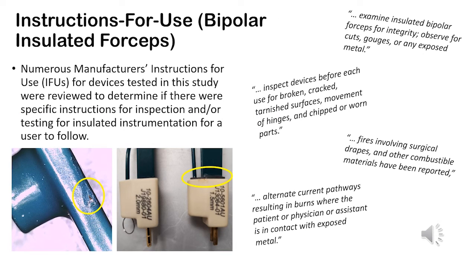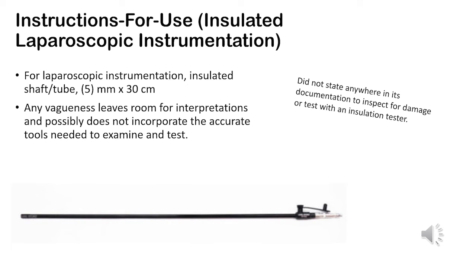The instructions for use were also reviewed for bipolar forceps. You can see some of these quotes from the IFUs where it says examine insulated bipolar forceps for integrity, observe for cuts, gouges, or any exposed metal, inspect for cracks, tarnished surfaces. It also states that fires involving surgical drapes and other combustible materials have been reported. For IFUs for laparoscopic instrumentation, specifically the shafts, it didn't really state anywhere in the documentation to inspect for damage or even test. But again, there are a lot of IFUs from different vendors that may have a little bit more in-depth direction.